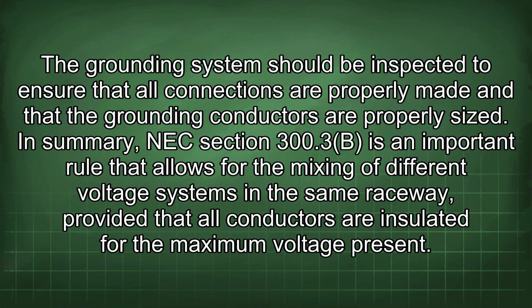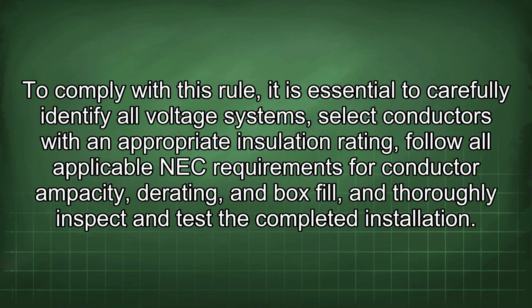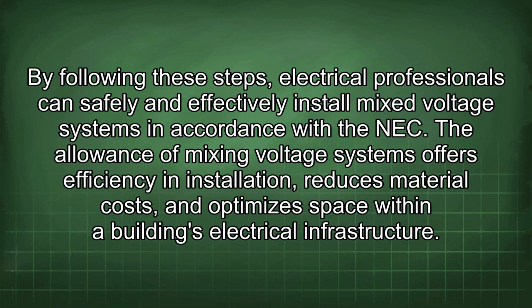are properly sized. In summary, NEC Section 300.3b is an important rule that allows for the mixing of different voltage systems in the same raceway, provided that all conductors are insulated for the maximum voltage present. To comply with this rule, it is essential to carefully identify all voltage systems, select conductors with an appropriate insulation rating, follow all applicable NEC requirements for conductor ampacity, derating, and box fill, and thoroughly inspect and test the completed installation. By following these steps, electrical professionals can safely and effectively install mixed voltage systems in accordance with the NEC.